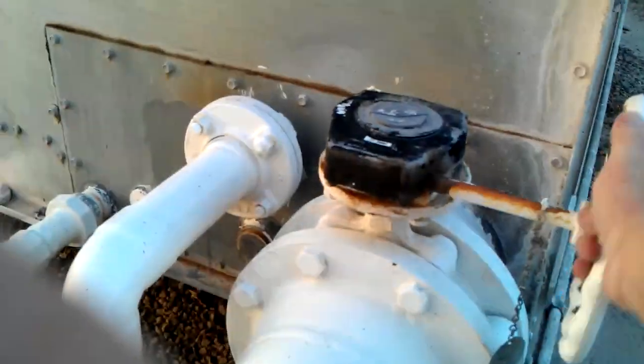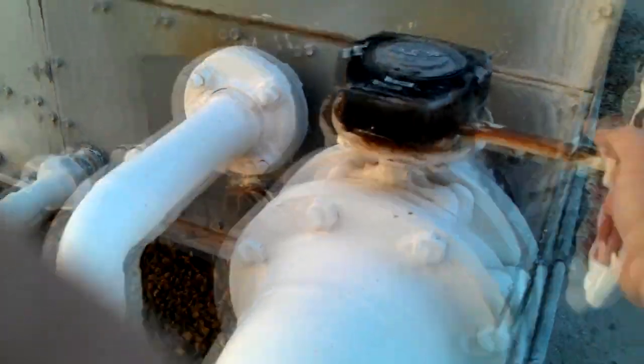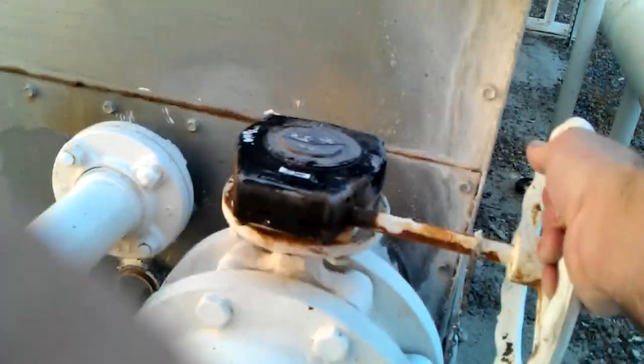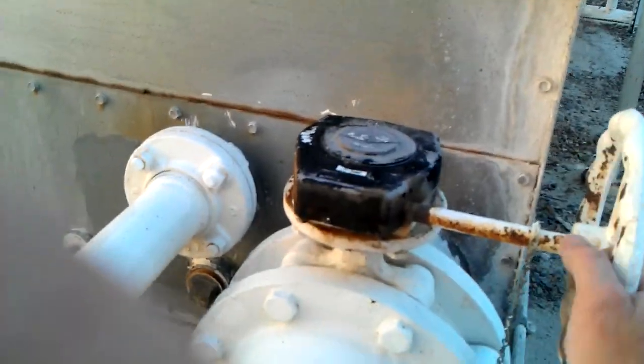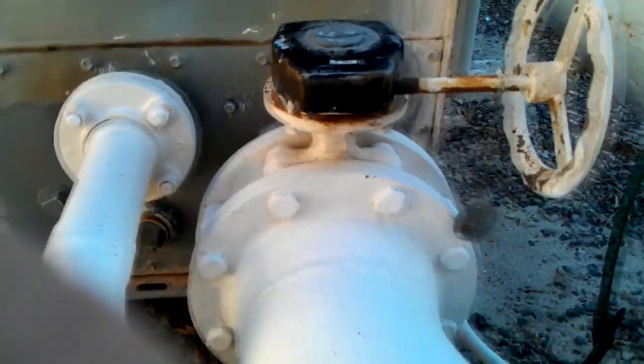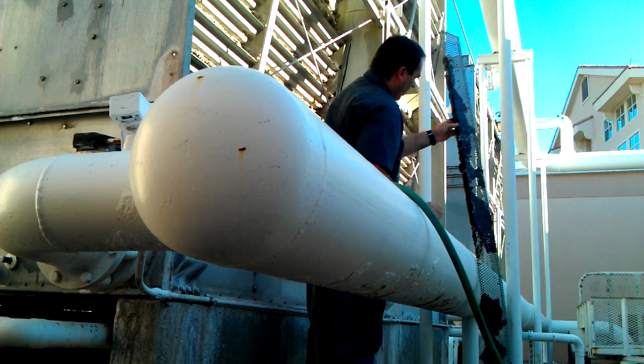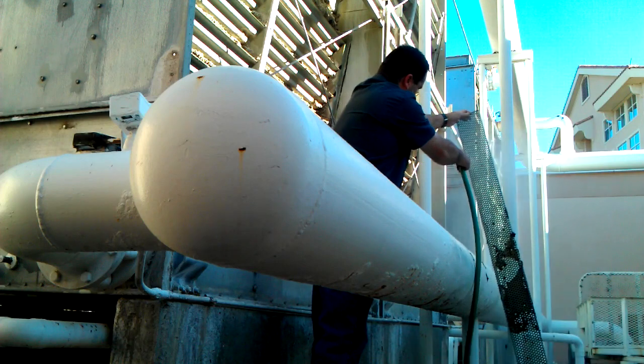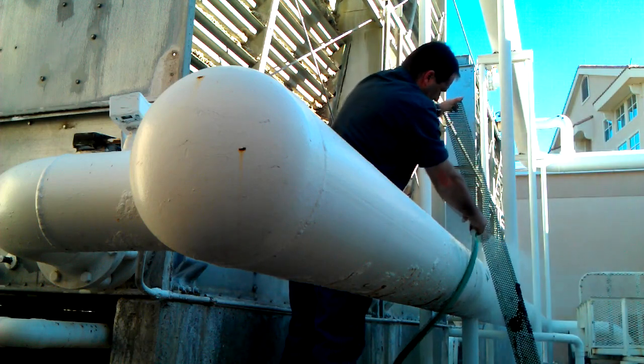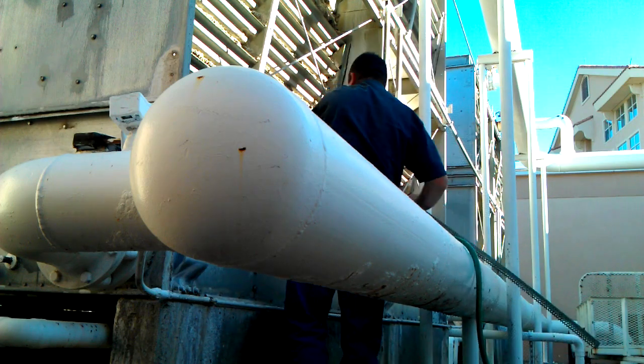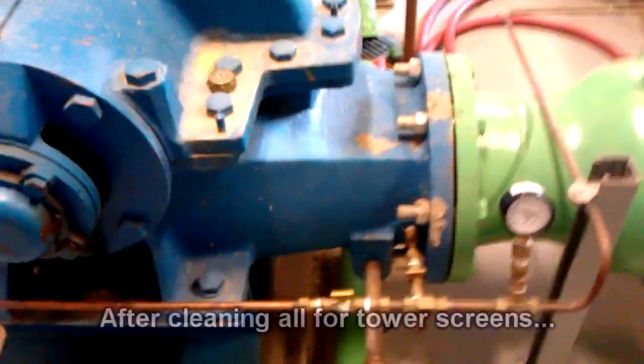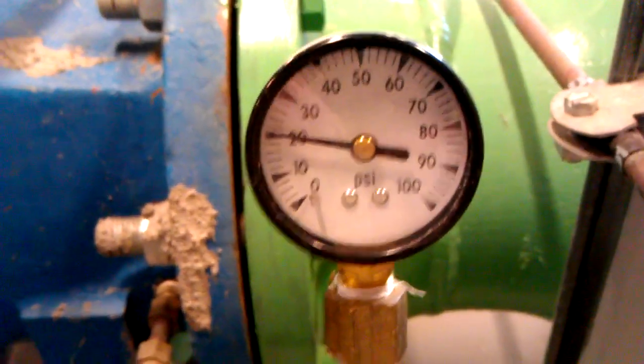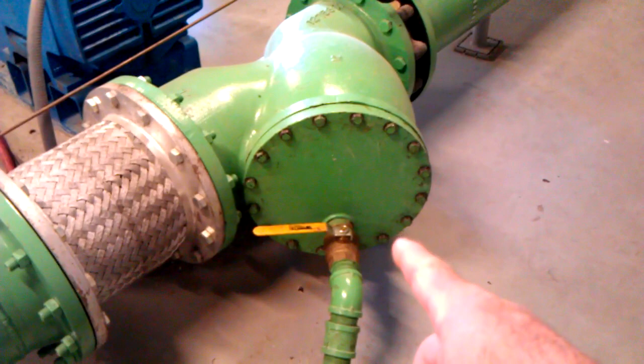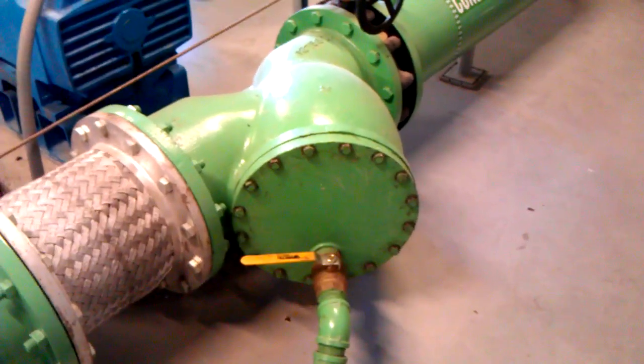Closing off the drain before I pull that screen out, because I can shut one drain at a time, no problem, and keep the system up and running. Kind of hard one-handed to do this. There we go. It is closed. Pressure is still low. There we go. So this screen is going to be loaded in there for sure.